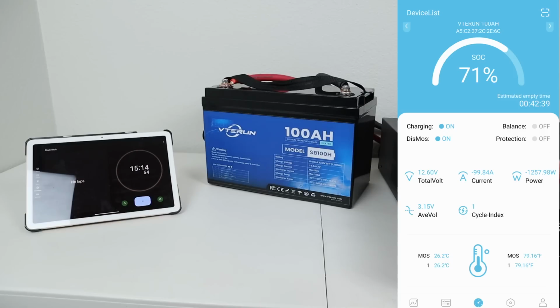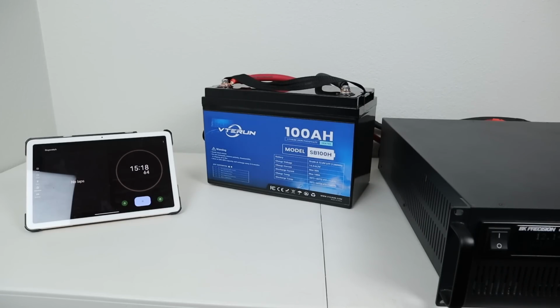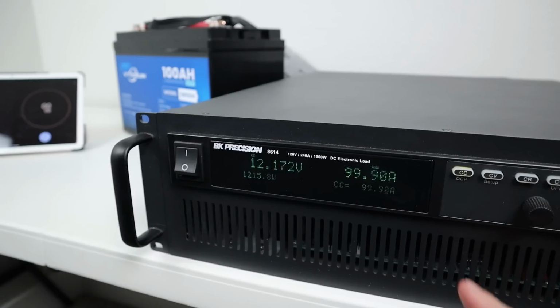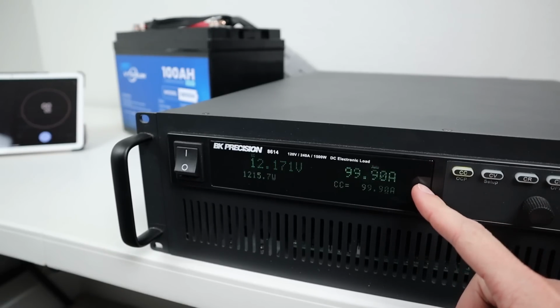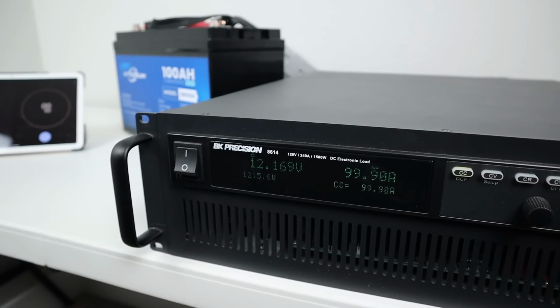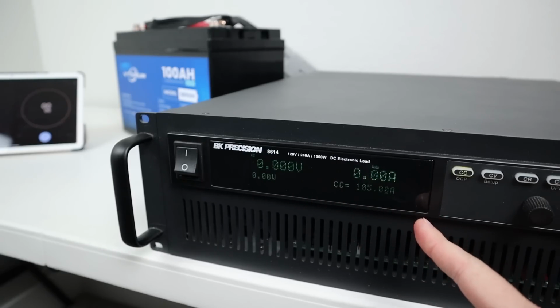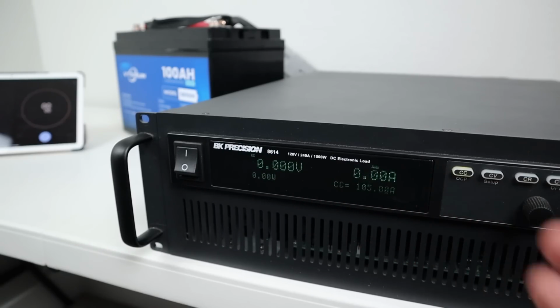Sorry, the fans on this unit are pretty loud when it's running this large of a load. But let's turn up the load to see if the BMS shuts off. So you can see the current load is 99.9 amps. So let's put in 105 amps and see if the BMS shuts off. Remember, it's rated for 100, so can we go over it? Oh, look at that. It instantly shut off. So anytime you go over 100 amps, the battery is going to shut off the BMS for discharging.